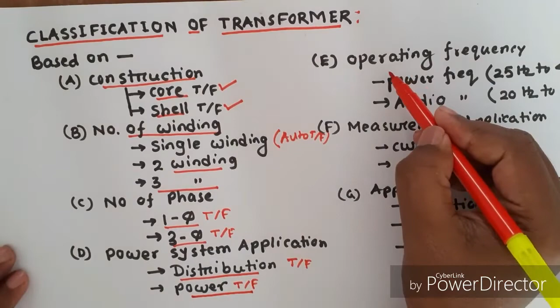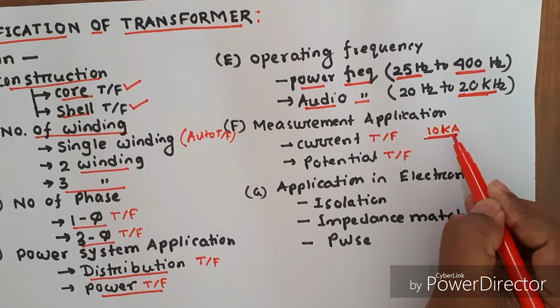Based on measurement application, it can be classified as current transformer and potential transformer. In the power system network, the current is very high, in the range of kiloampere - suppose 10 kiloampere. This amount of current cannot be measured with the help of a normal ammeter. Therefore, with the help of a current transformer, I reduce the current level and measure the current. Similarly, for measurement of high voltage, we use the potential transformer.